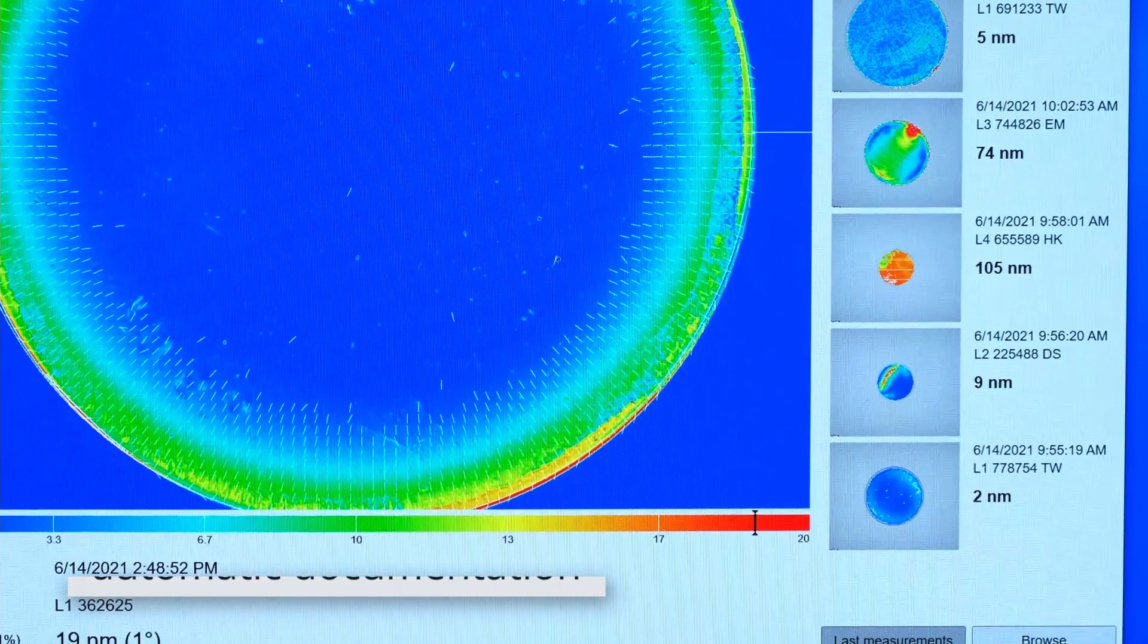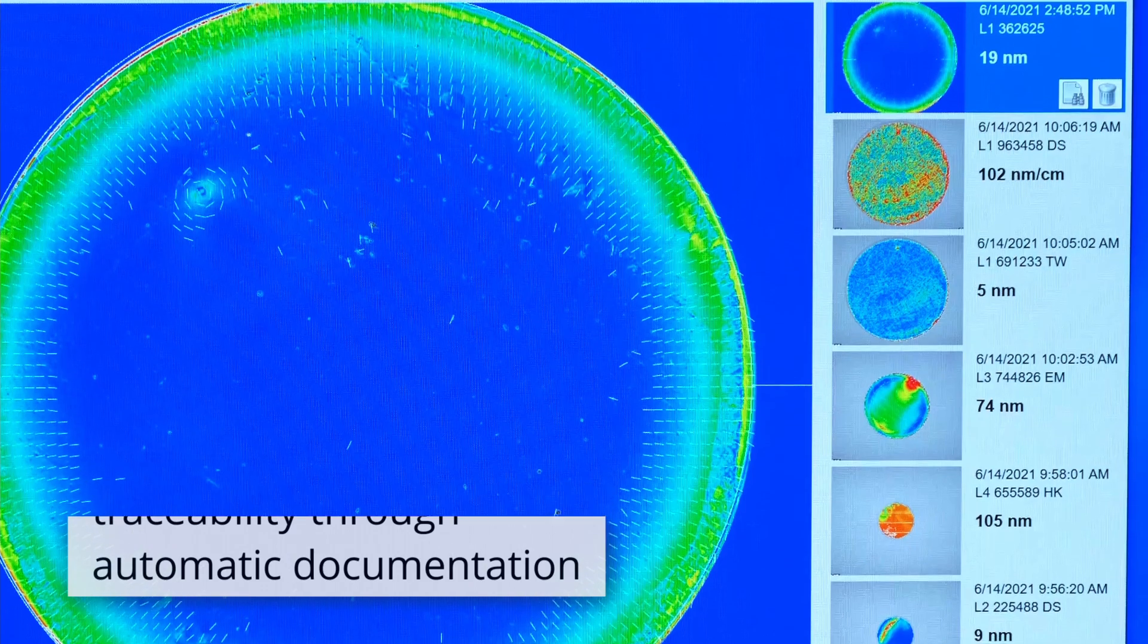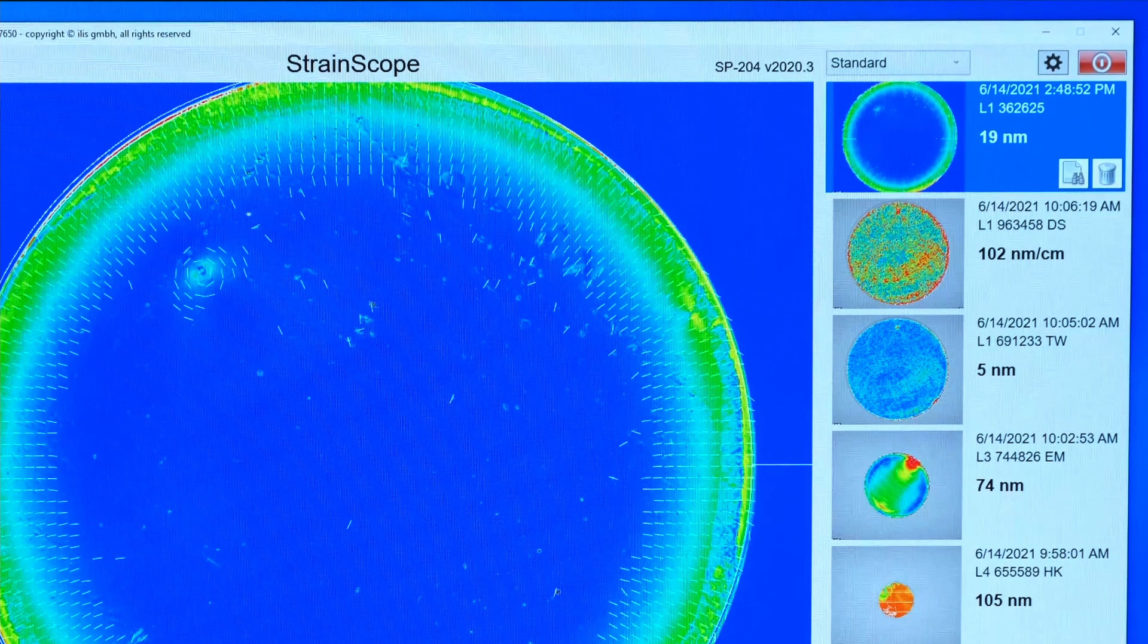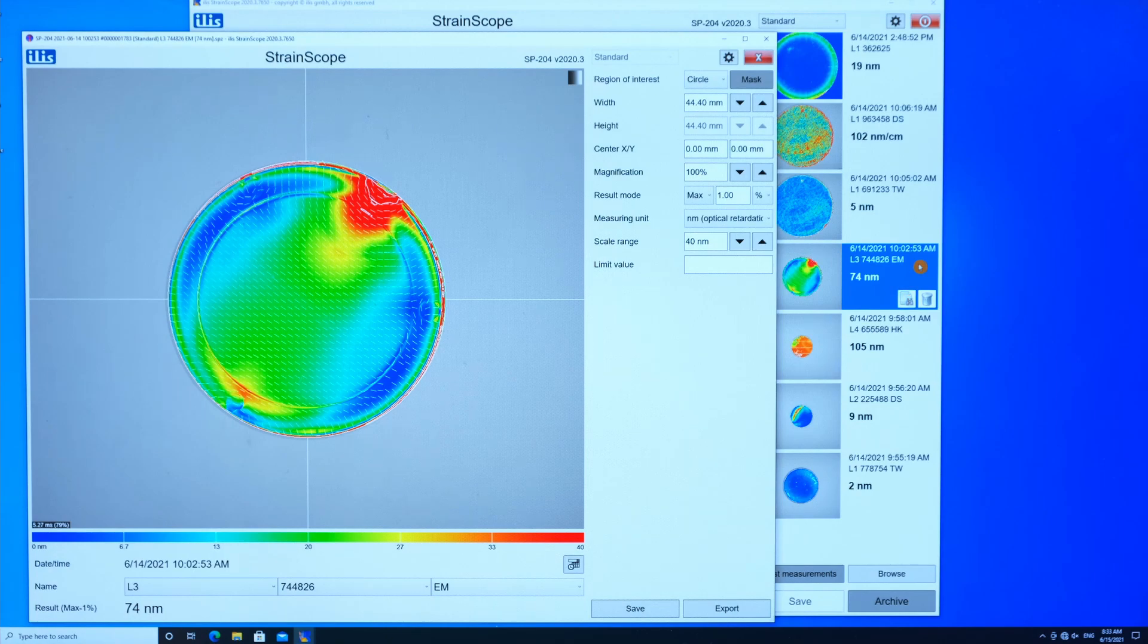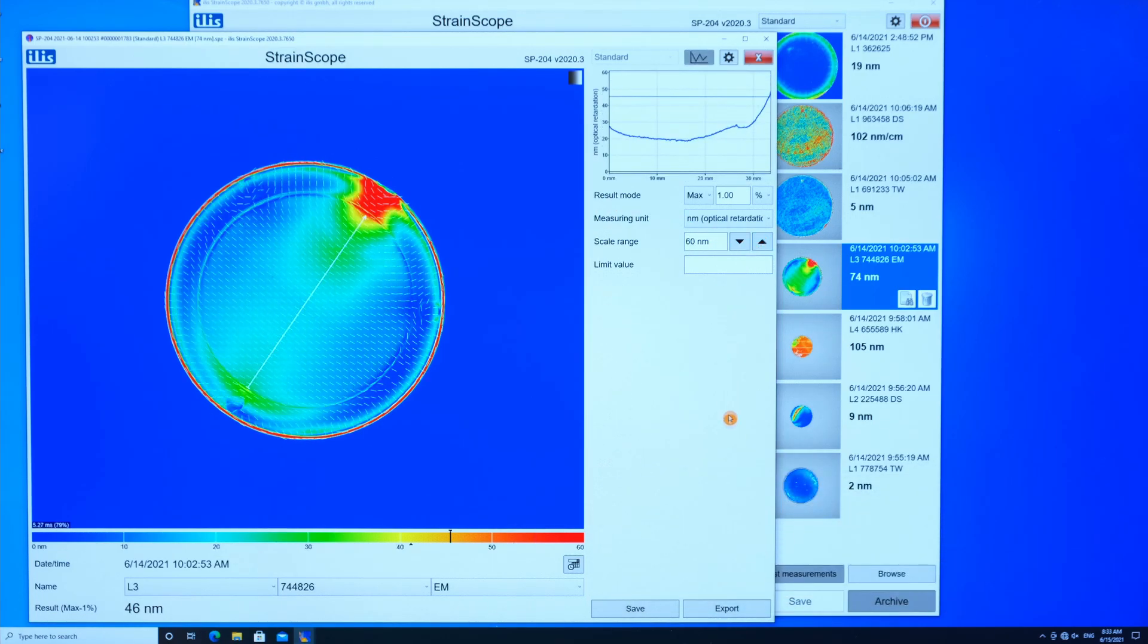Measurements can be saved in the integrated archive. This ensures complete documentation and traceability of all results. The saved raw data can be further processed and evaluated in the StrainScope software or converted into an open file format using the convenient export function.